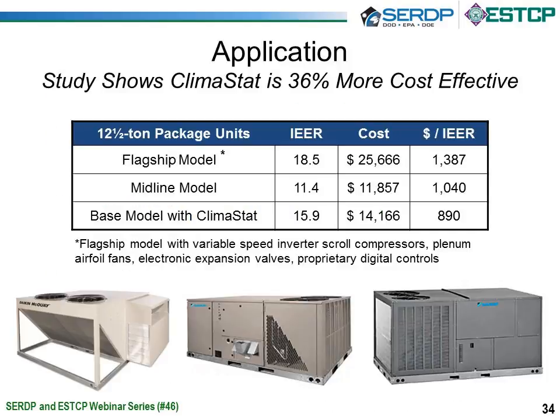As for application, the study shows that ClimaStat is 36% more cost-effective as a way of achieving higher energy efficiency. Comparing 3 units here, we have the flagship model versus a midline model versus a base model with ClimaStat installed, a ClimaStat equipped base model. So if we look at a flagship model, which is maybe kind of like the Ferrari or the Corvette of air conditioners here, has a very high IEER, but the cost is also very high. And if we look at the ratio of the cost per amount of efficiency points you're getting, it's about $1,387 per EER point.